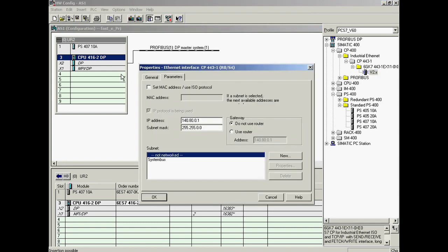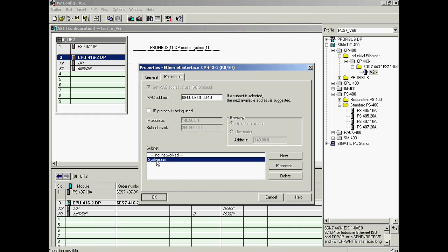Next, the communications processor CP443-1 is inserted for Ethernet communication. Various settings are defined in the properties dialog: first, the ISO protocol is activated and the MAC address is entered. The IP protocol is not used, so it is deactivated. Finally, the communications processor is assigned to the system bus network.